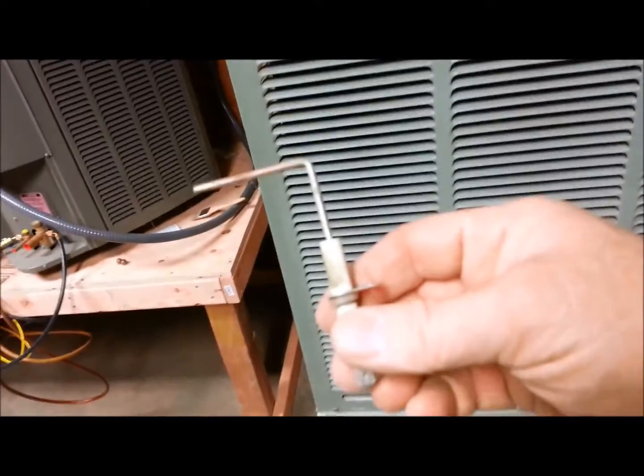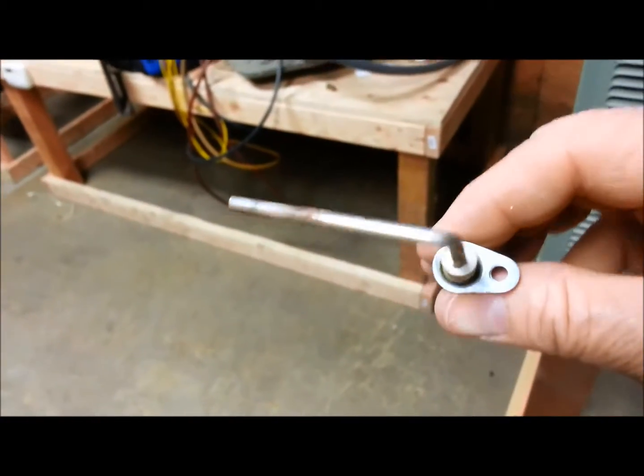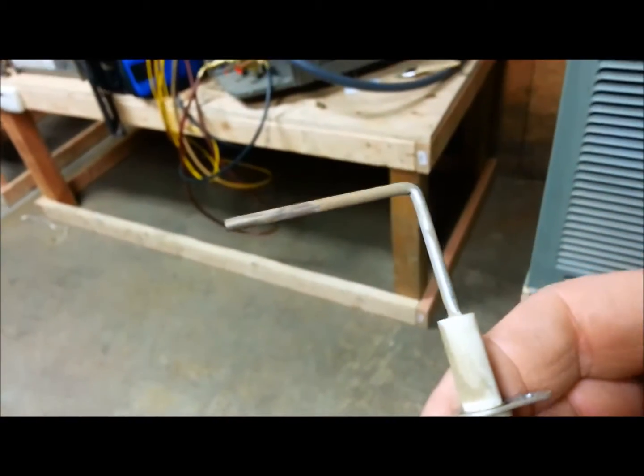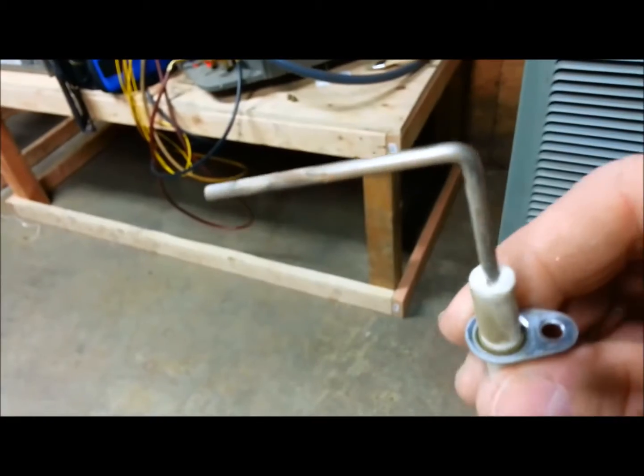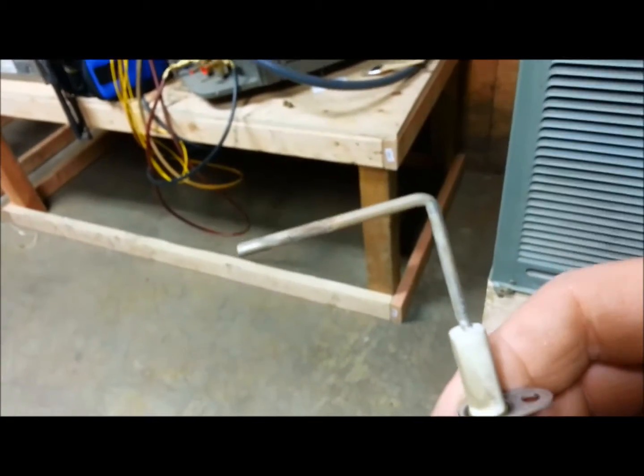Okay, I removed the flame sensor and as you can see it's pretty dirty and rusty. We'll go ahead and polish it up and stick her back in and let's see what kind of reading we get.